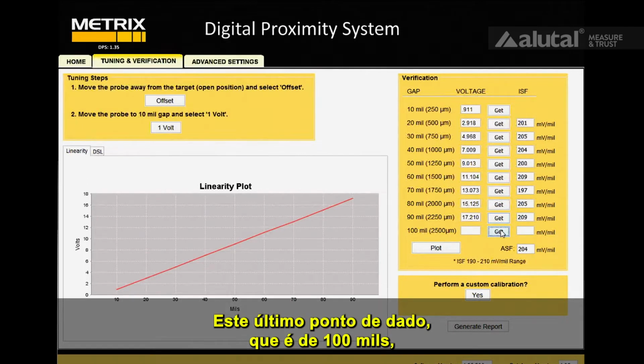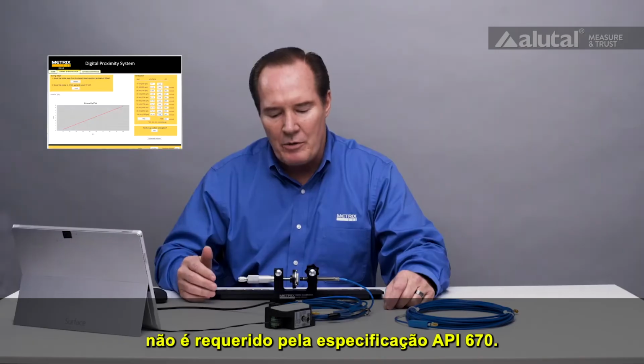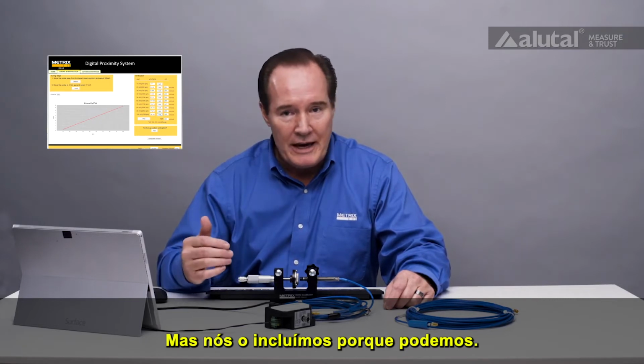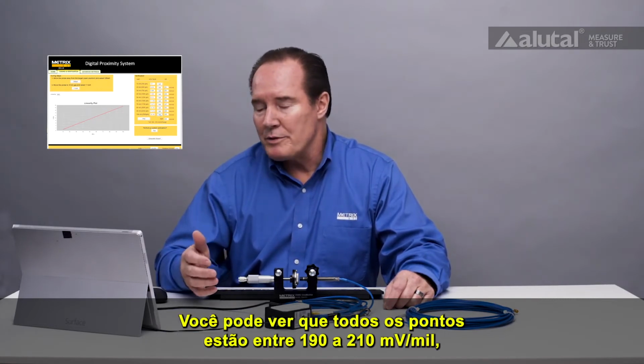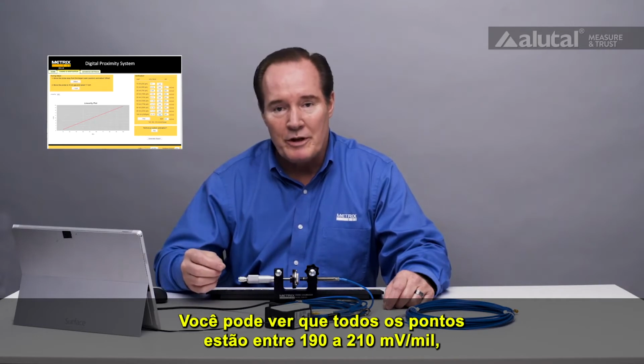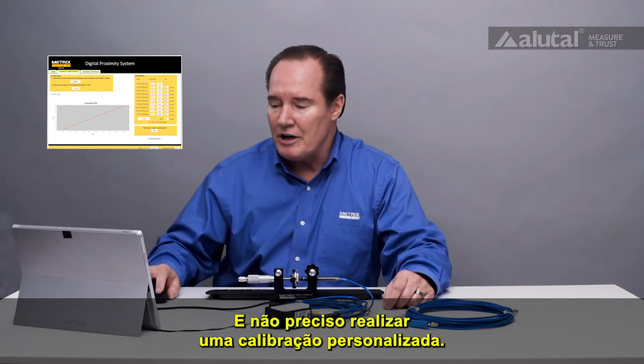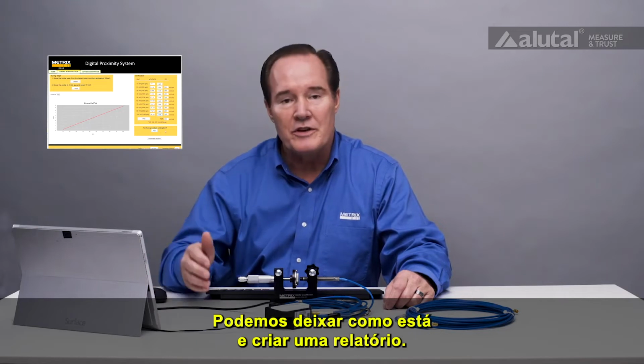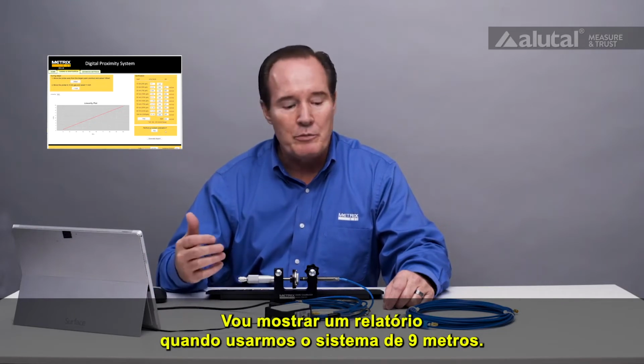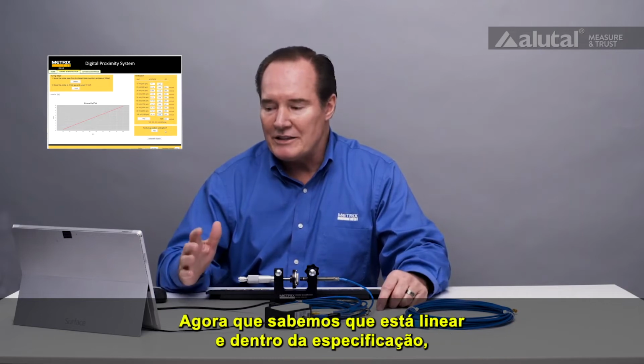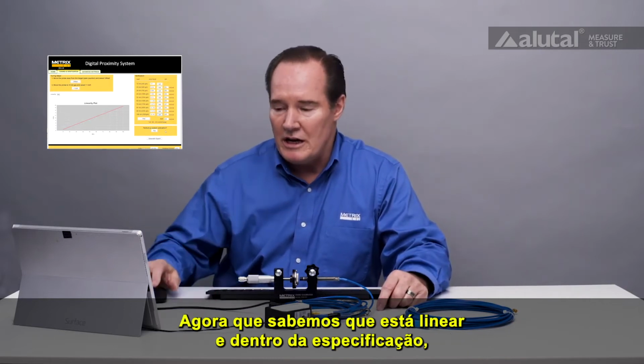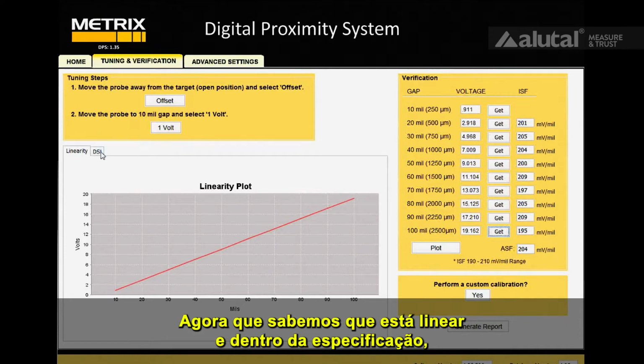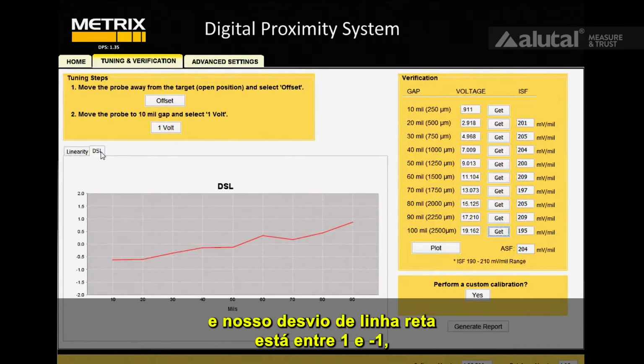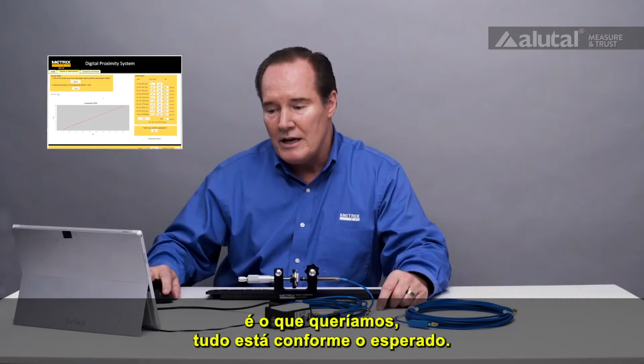On this last point, which is 100 mils, it's actually not required by the specification, API 670. But we include it because we can. What you see is that all the points are between 190 and 210 millivolts per mil, so it's well within specification, and I don't need to perform a custom calibration. We can just live with it, and we can create a report. And I'll show you a report when we do the 9-meter system. But what I'd like to do now is, since we know this is linear and it's well within the specification, and our deviation from straight line is between 1 and -1, that's what we wanted.